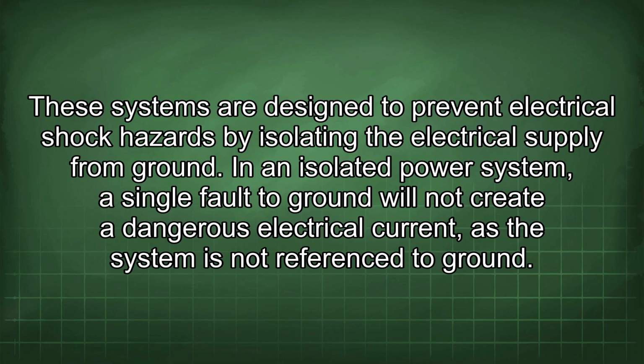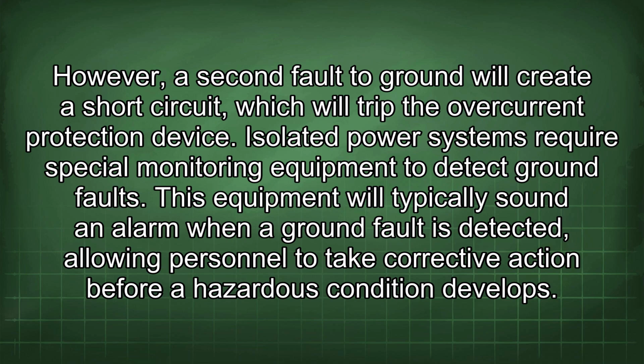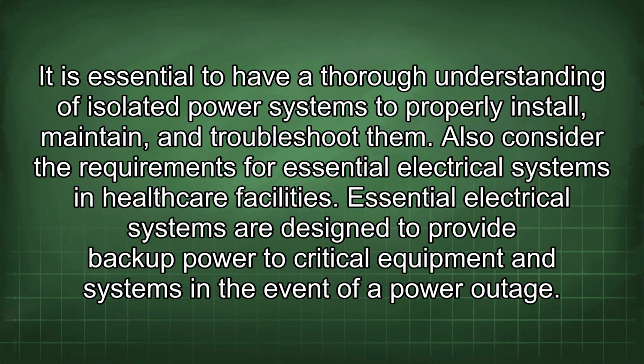In an isolated power system, a single fault to ground will not create a dangerous electrical current, as the system is not referenced to ground. However, a second fault to ground will create a short circuit, which will trip the overcurrent protection device. Isolated power systems require special monitoring equipment to detect ground faults. This equipment will typically sound an alarm when a ground fault is detected, allowing personnel to take corrective action before a hazardous condition develops. It is essential to have a thorough understanding of isolated power systems to properly install, maintain, and troubleshoot them.